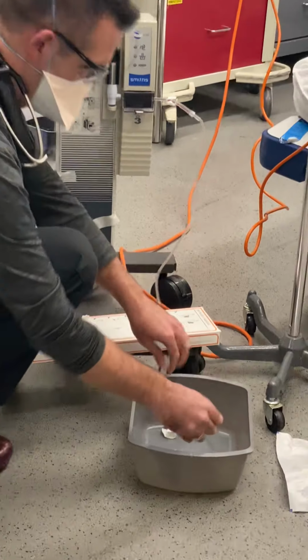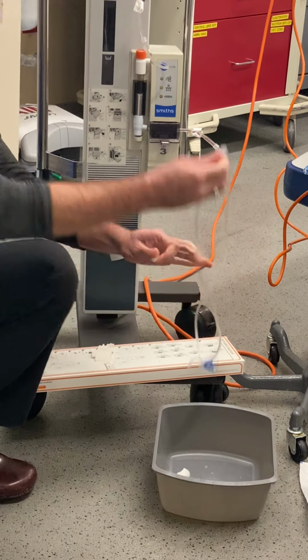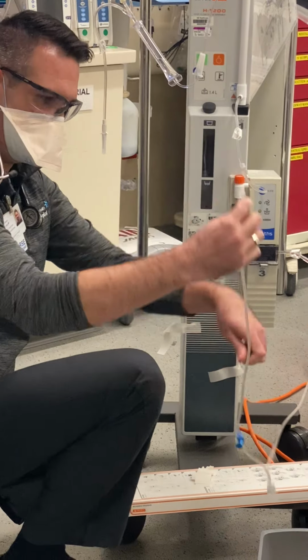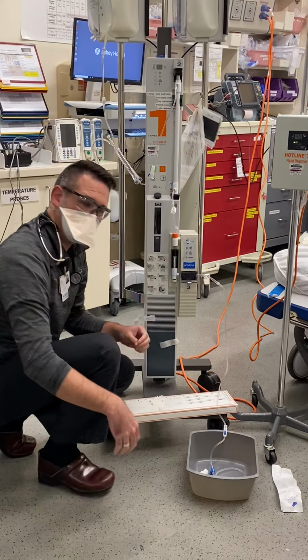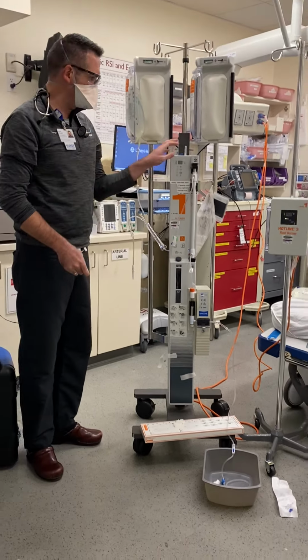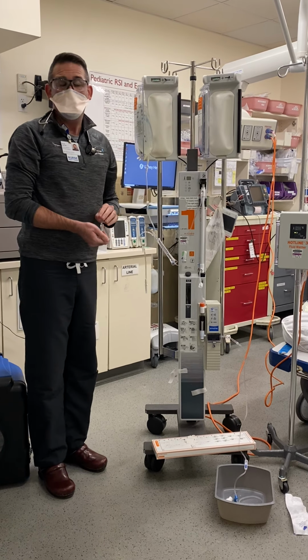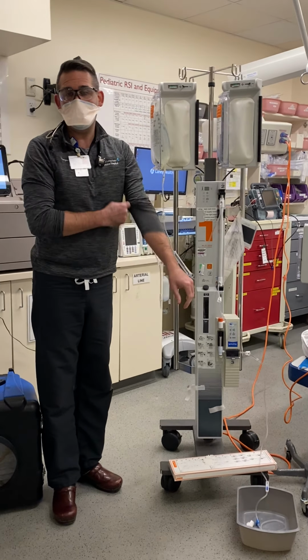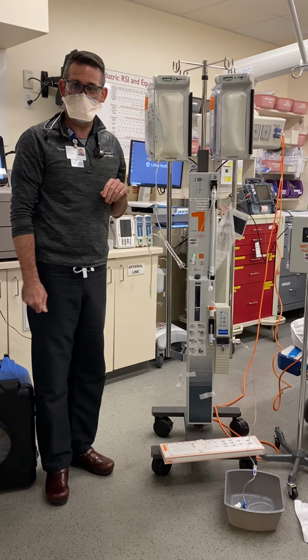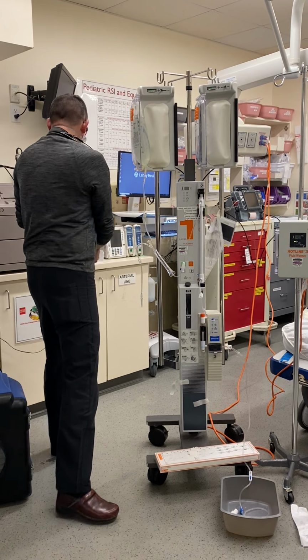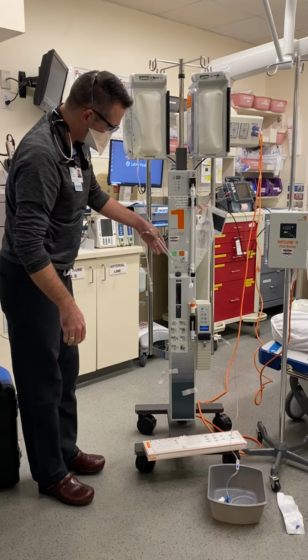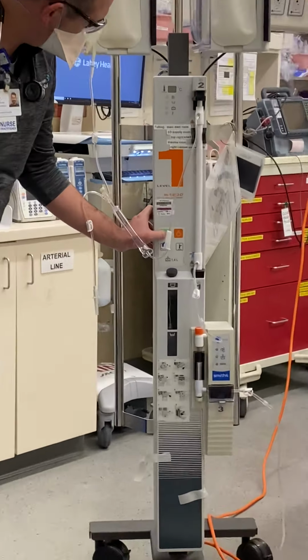All right, now I'm going to put this down here, and this is where you would attach it to the patient's IV. You need to have a large bore IV to use this because a lot of pressure gets generated. Nothing smaller than an 18 should be used with the level 1. So if you want to start to use it for its 2 intended functions, turn it on by pushing the green button.